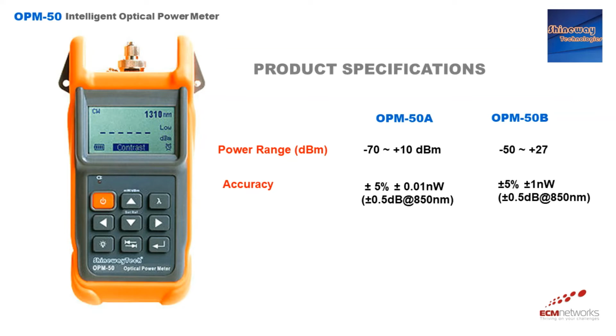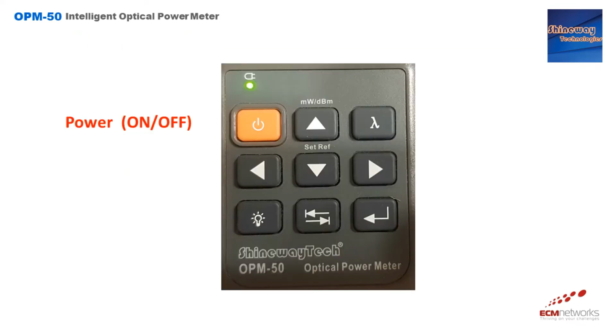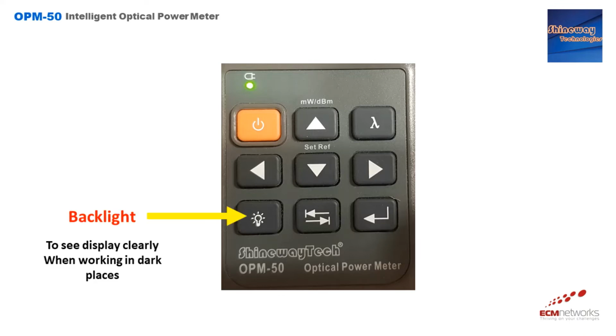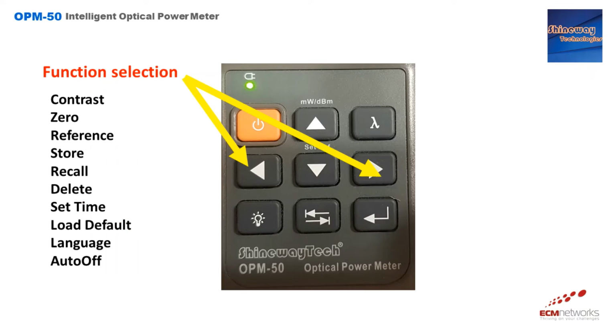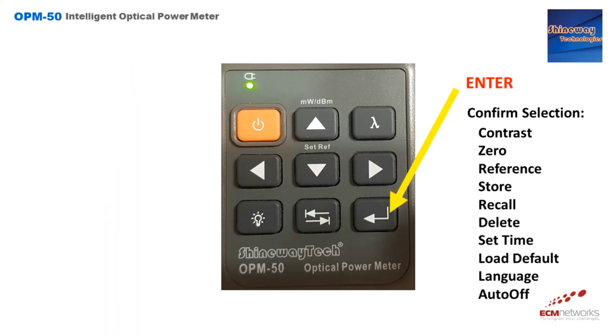±5% ±1 nanowatt. Here are the functions of the OPM50 keypads. The orange button is to turn on and turn off the equipment. If working in dark test sites, you can turn on the LED backlight to see the display clearly. The left and right arrow keys are used to select the function like contrast, zero, reference, store, recall, delete, set time, load default, language, and auto-off. The enter key is pressed to confirm selection of a function.